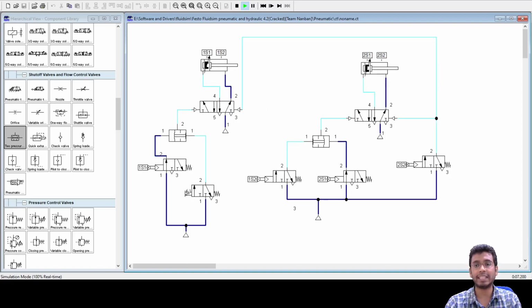Why did my second cycle not execute? Because this line has to be a pressurized line, only then will this valve shift, and then all the circuit is controlled from here onwards. Because of the push button, when I pressed, I got a signal from here which resulted in this pilot signal here, but the moment I pushed and left it back, this spring offset closed this pressurized port here, and I do not have any signal back here.